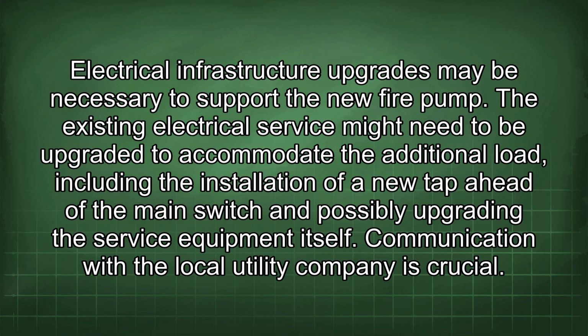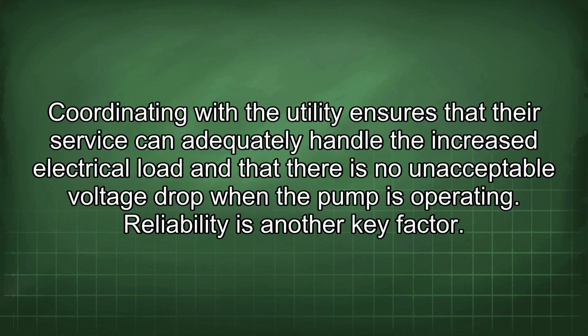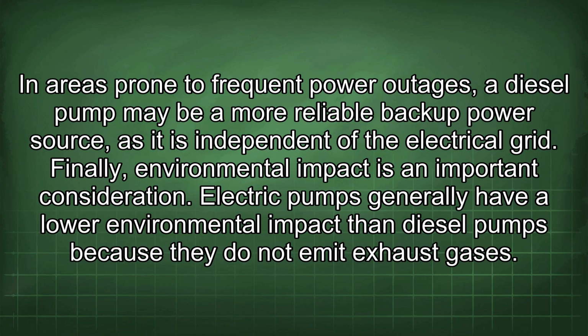Communication with the local utility company is crucial. Coordinating with the utility ensures that their service can adequately handle the increased electrical load and that there is no unacceptable voltage drop when the pump is operating. Reliability is another key factor. In areas prone to frequent power outages, a diesel pump may be a more reliable backup power source, as it is independent of the electrical grid.